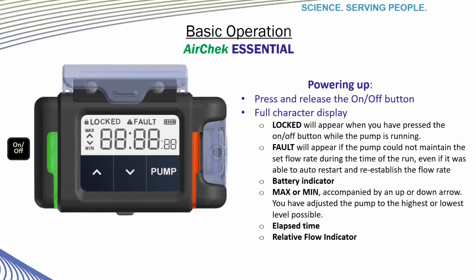Next to that, you will see fault, and that will appear next to a small hazard triangle anytime the pump has gone into flow fault during a run. This will remain in the display even if the pump was able to auto restart and reestablish the flow rate. This is so that you will know that the pump has faulted at some point, and you may need to evaluate whether you have a valid sample. It is important to note that the elapsed time clock will freeze when the pump goes into flow fault, and then it will resume once that has been reestablished. So the flow time on the display will be the amount of time that the pump ran properly.